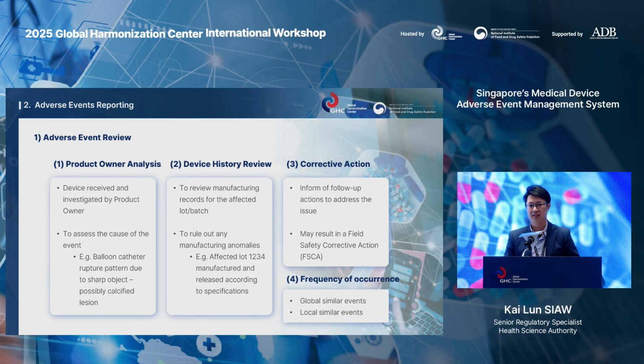Apart from product device analysis, we also look at the device history review. For reported affected lots, the company will have to refer back to their records for any manufacturing anomalies. This is to rule out any defects during manufacture. If yes, then they have to follow through with enhancements to their manufacturing processes. Lastly, after considering all factors, they have to inform us of any follow-up actions they intend to do. This may normally result in a field safety corrective action. If it's a systemic design issue, they will probably have to recall the device. If it's a manufacturing process error, as mentioned, then they have to enhance their manufacturing process.